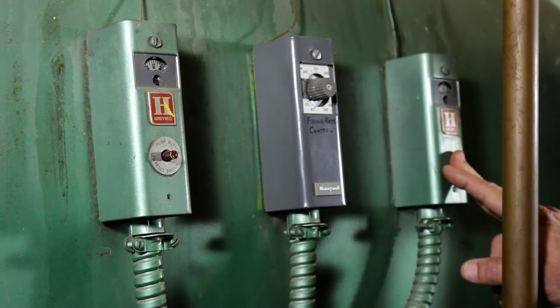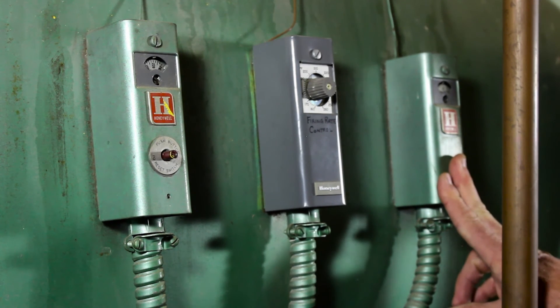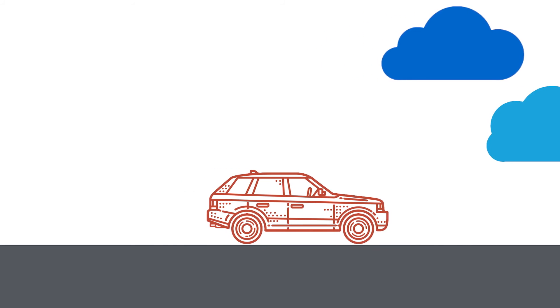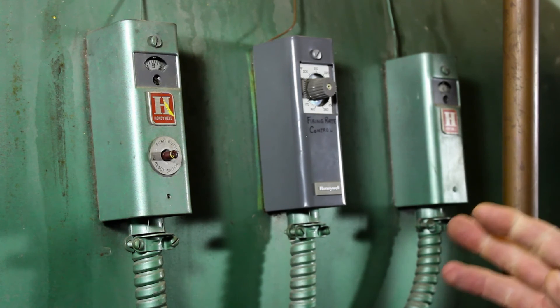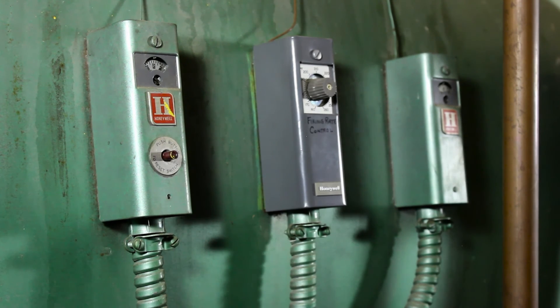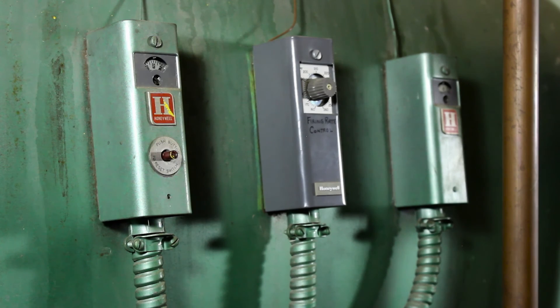It's really similar to trying to control your car by starting the engine and slamming the gas to the floor, and before you get to the speed you want, you shut the engine off — then keep your foot on the gas pedal and start the car again. That's kind of the way it functions. So you'll notice your boiler is short cycling, it consumes more energy because there's excess post-purge and pre-purge, and a lot of times you can't even satisfy your building load.